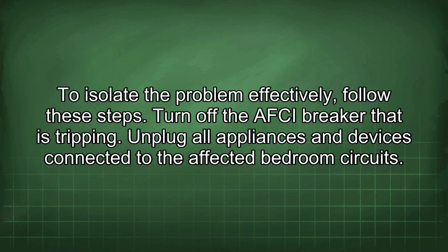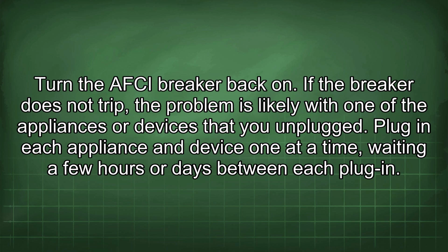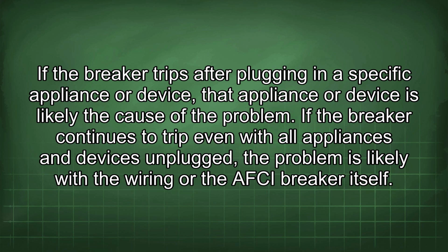Turn off the AFCI breaker that is tripping. Unplug all appliances and devices connected to the affected bedroom circuits. Turn the AFCI breaker back on. If the breaker does not trip, the problem is likely with one of the appliances or devices that you unplugged. Plug in each appliance and device one at a time, waiting a few hours or days between each plug-in.